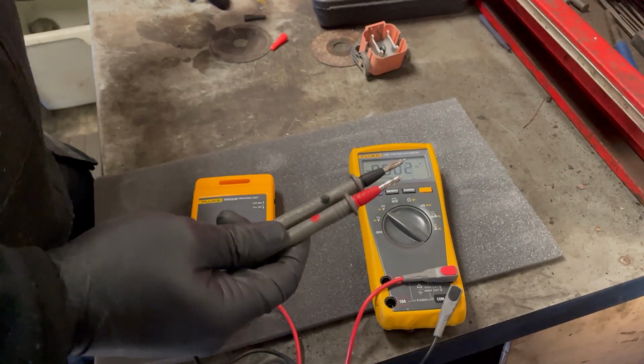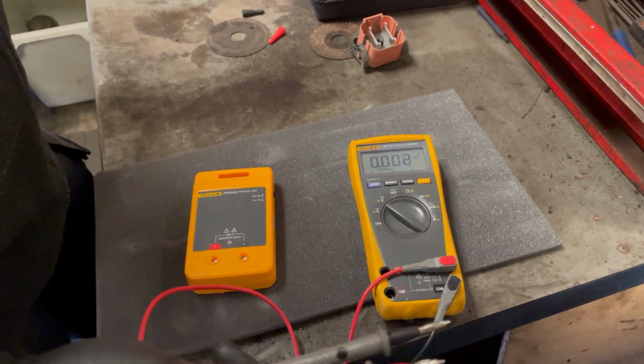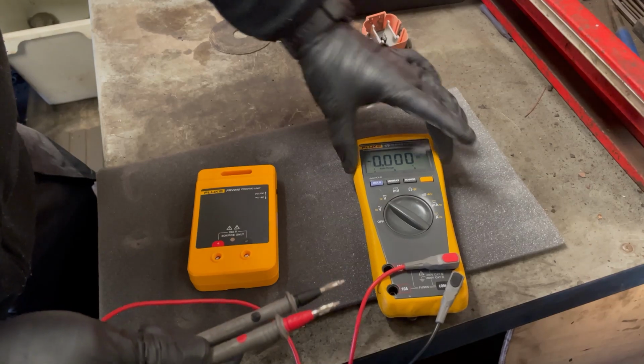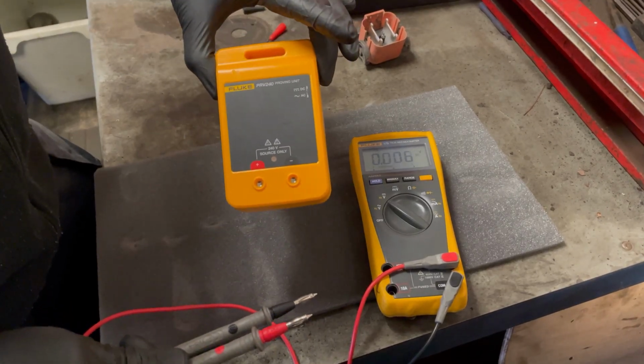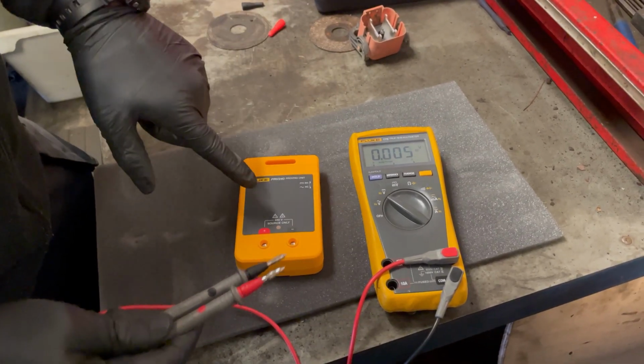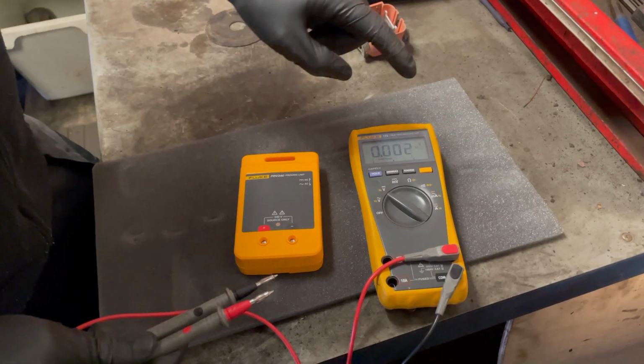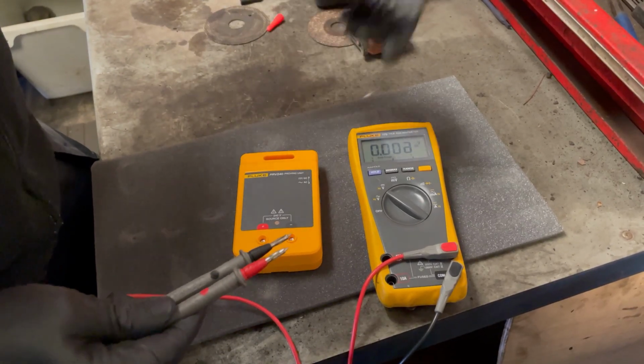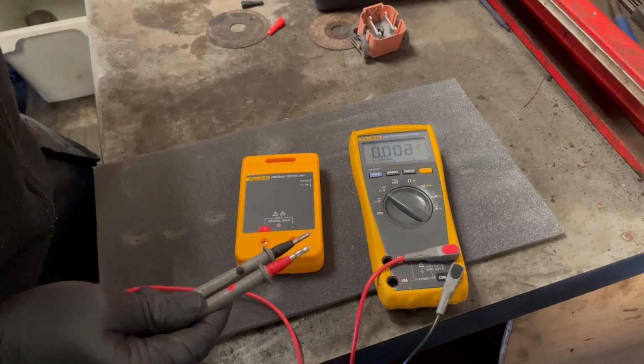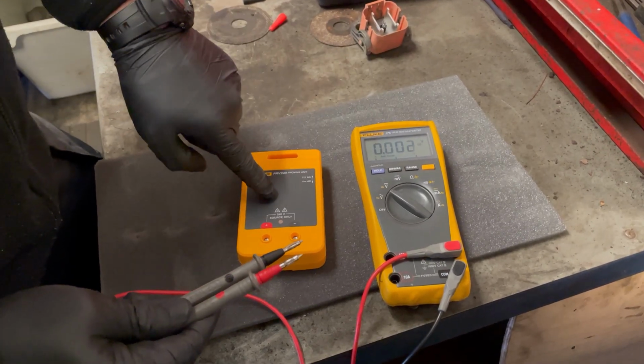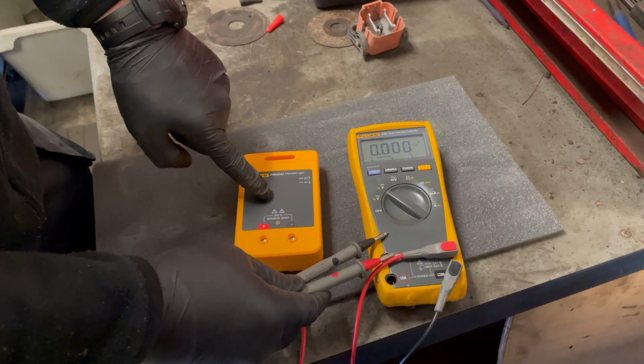Of course, before we do the check on the battery to make sure there's an absence of voltage, we need to make sure this multimeter is working correctly. So I'm going to use this proving unit from Fluke. Essentially this puts out 240 volts, so we'll check it says 240 there. We'll then check that it says 0 volts on the big battery, and then we'll come back and double check that the multimeter hasn't blown while doing the second test.